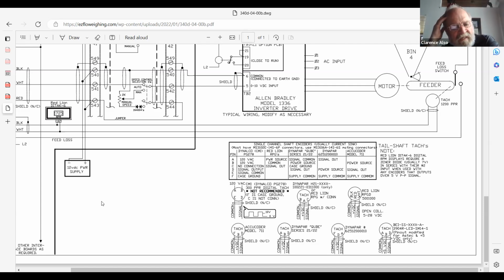That's important to do. With the scales we do, and the shielded wire, what we do is just shield there at the indicator, then it goes to the plug on its own, and then to a shield terminal, but you don't ground it at that far end. Anyhow, that's a good point. Thank you. Also, thermocouples, same way.